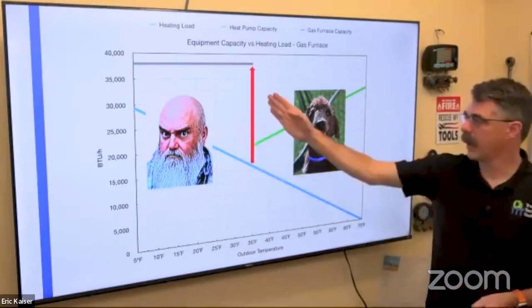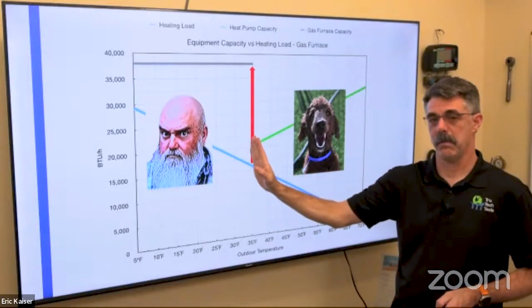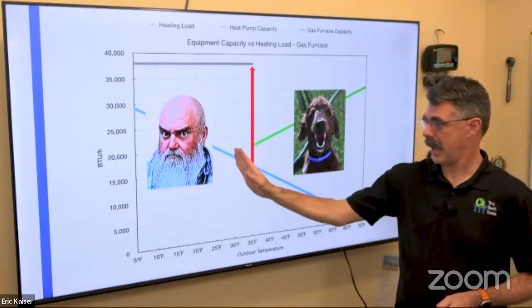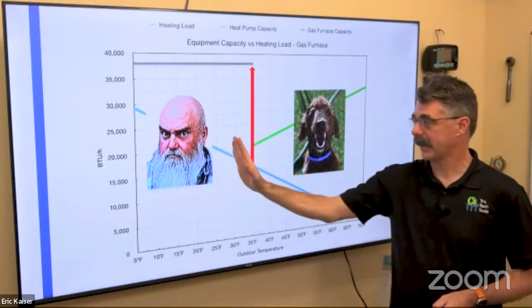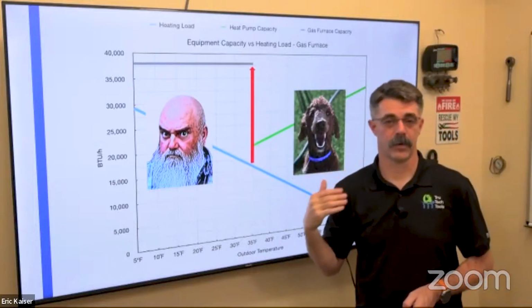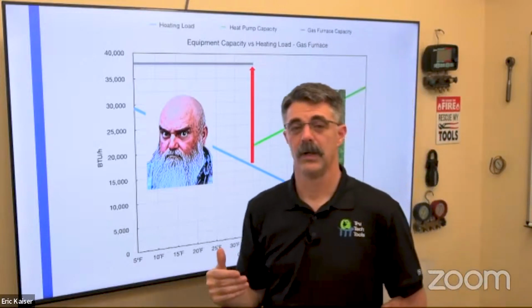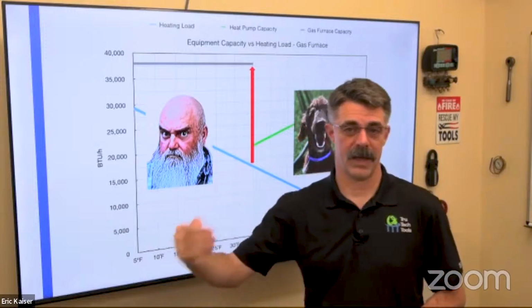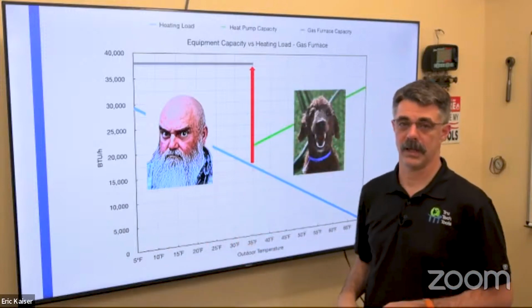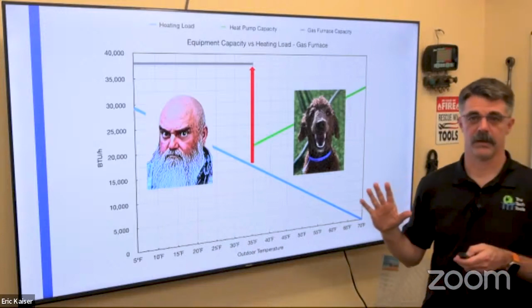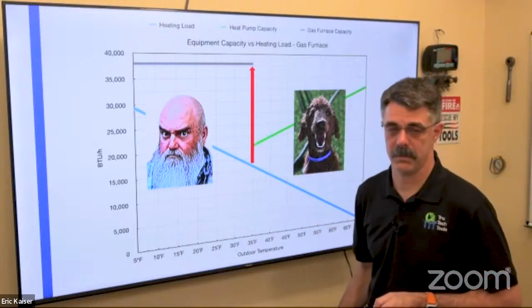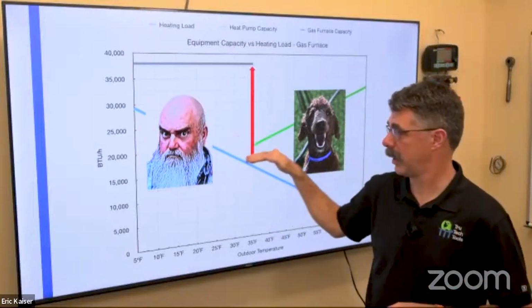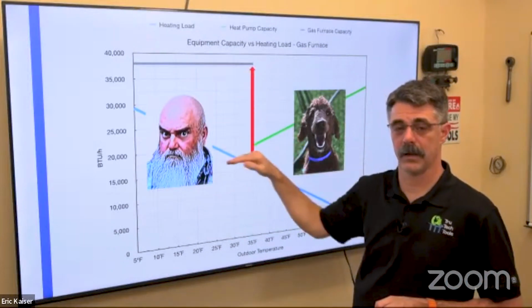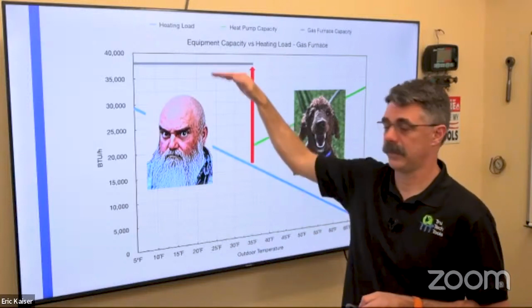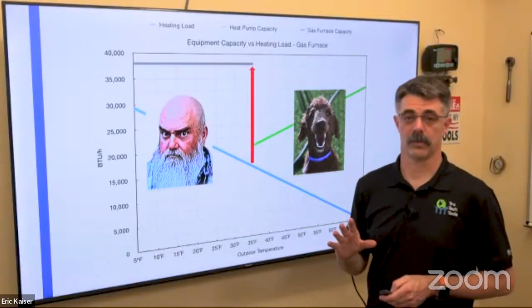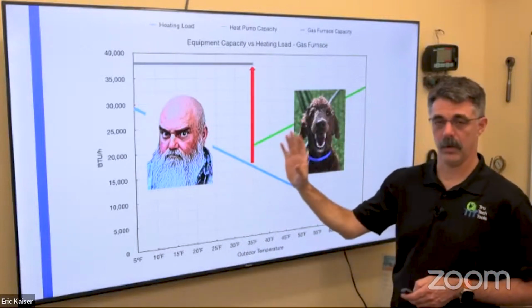So we got to know where to set that. One of my solutions was I actually backed that transfer up a little bit because I had it set hard on that performance line. Back that up a little bit so that the gas furnace would transfer a little bit sooner. And I didn't have that hard cliff essentially hitting that. So a little bit different, couple ideas. If you're going with dual fuel, this may be a concern. You may also want to look at a 2-stage to where it kicks down here to second, and then it's running first stage a lot, and it's cycling second stage off and on. But you've got to get a small 2-stage sometimes, depending on the load of the house.